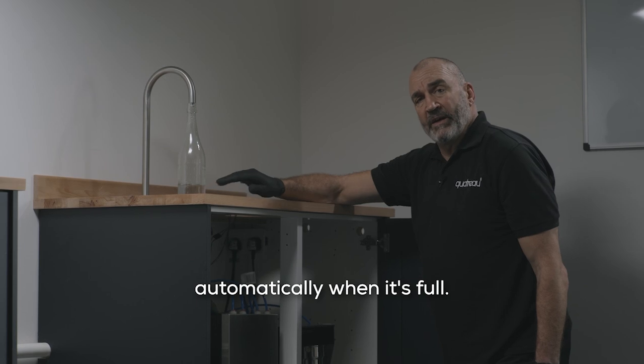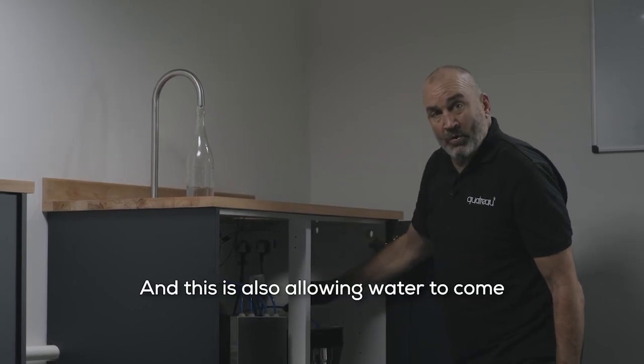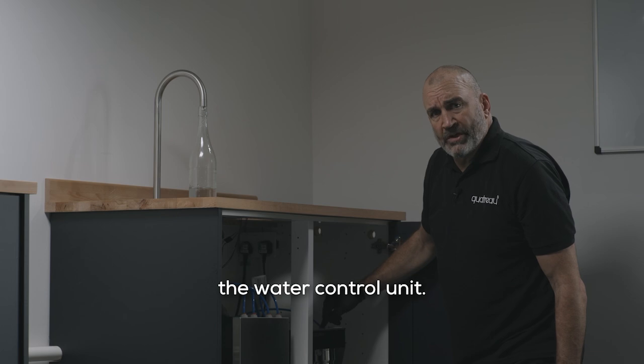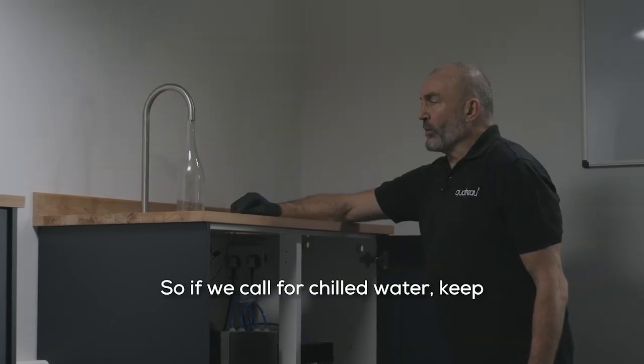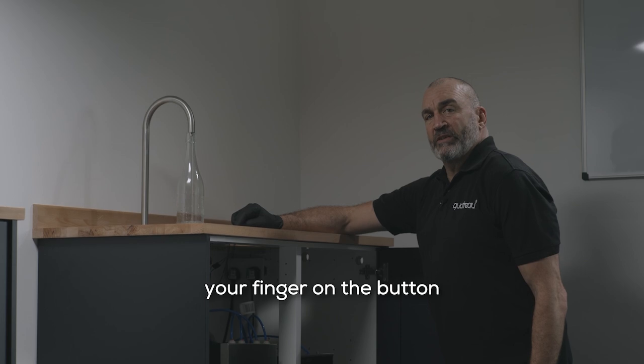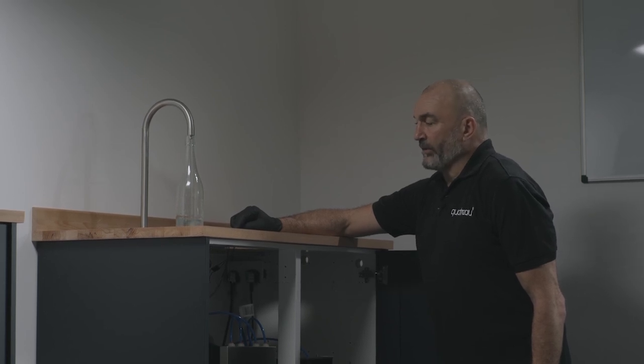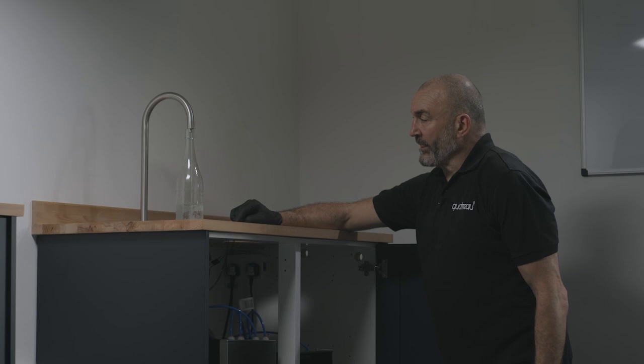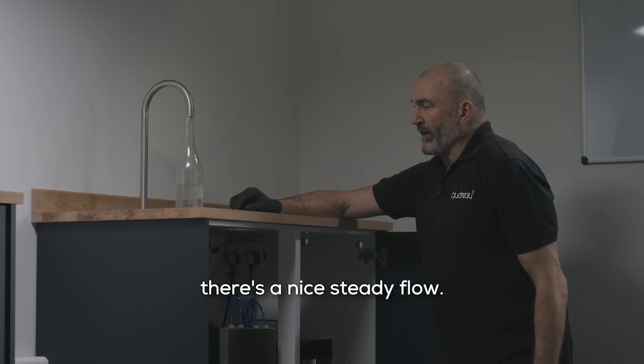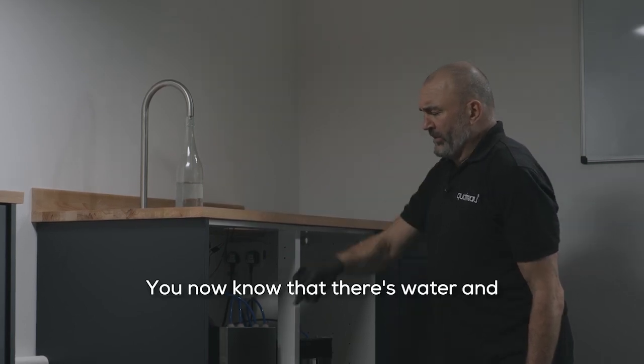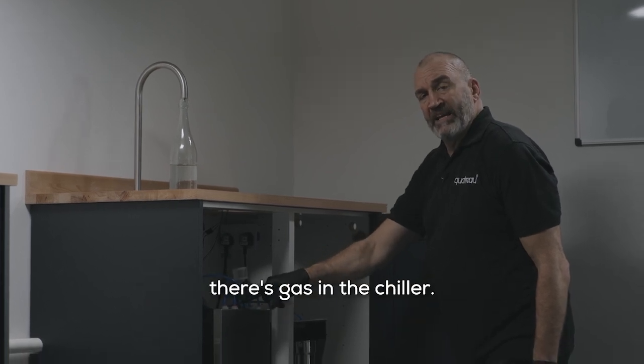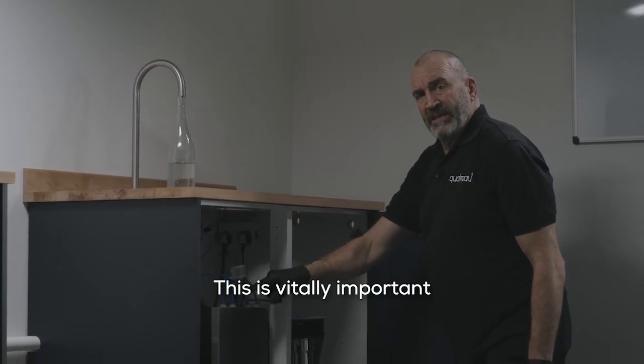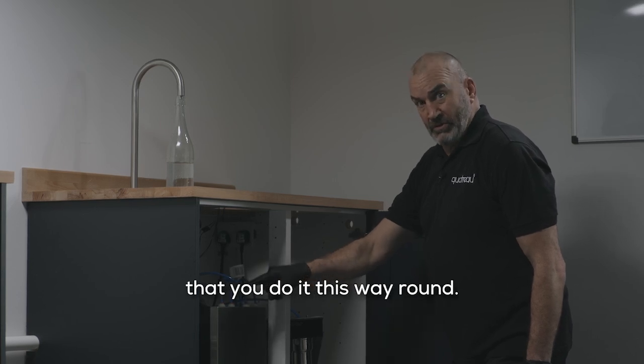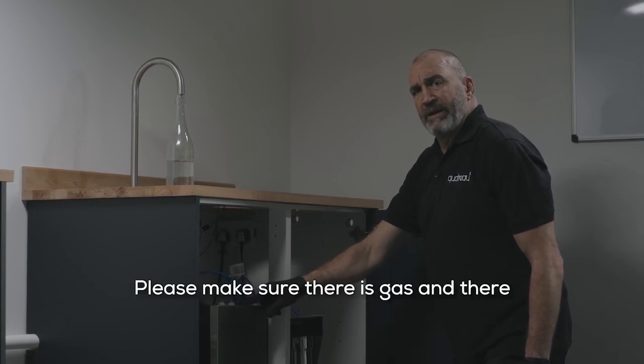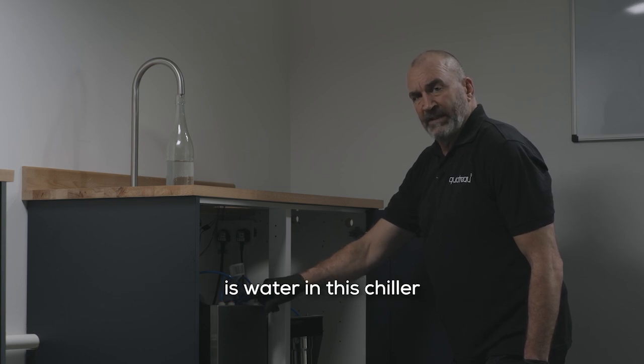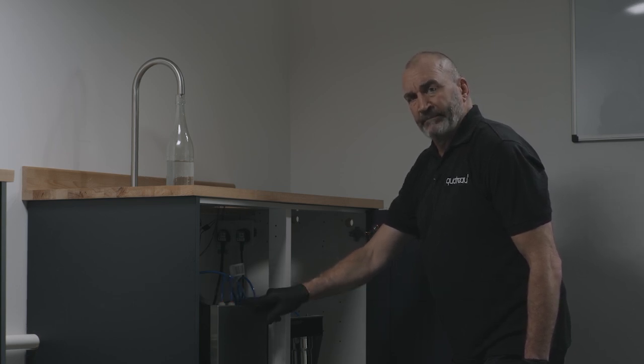This will shut off automatically when it's full, and this is also allowing water to come down and start feeding the water control unit. So if we call for chilled water, keep your finger on the button till you get a nice steady flow. Make sure there's no spluttering. Once you're happy there's a nice steady flow, you now know that there's water and there's gas in the chiller. This is vitally important that you do it this way round. Please make sure there is gas and there is water in this chiller before you go any further.